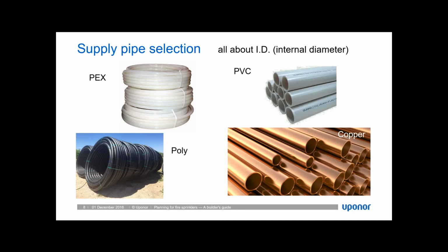The internal diameter of PVC and copper is often going to be larger than the internal diameter of PEX or various kinds of poly. So where a 1 inch PVC underground supply may be more than okay as far as how much pressure we're losing, the same distance of 1 inch PEX or poly would lose significantly more of your available pressure. This is because as we're flowing water through the pipe, you're losing some of your pressure for every foot that you're traveling down the pipe.